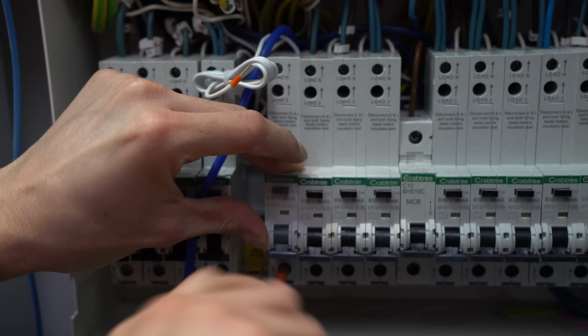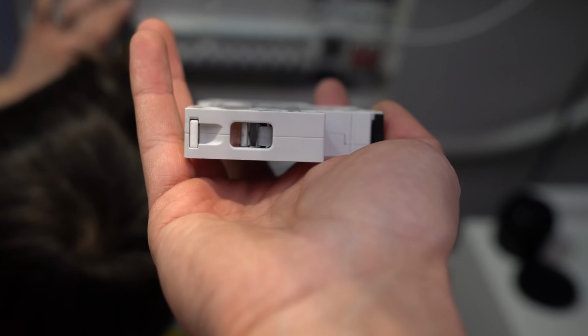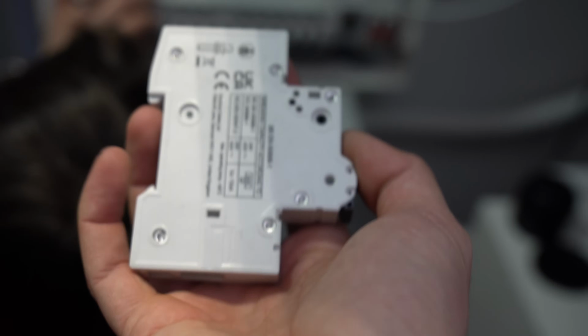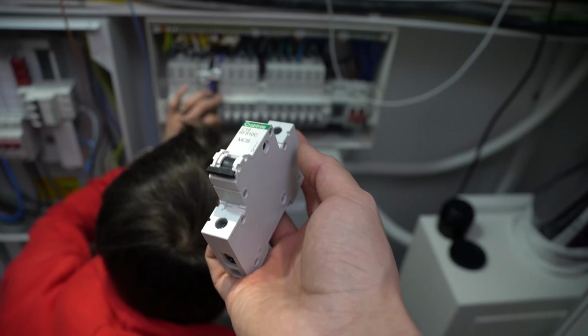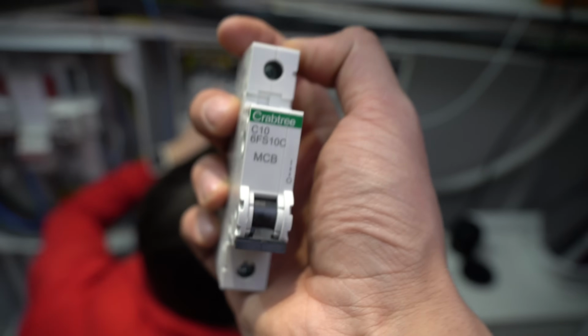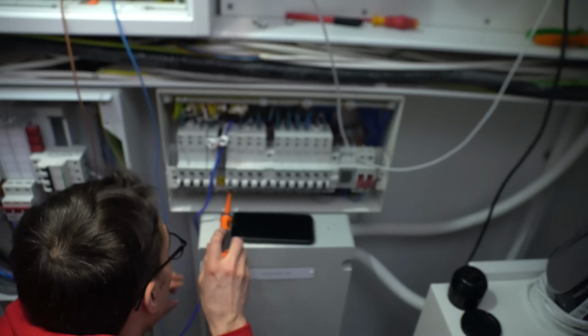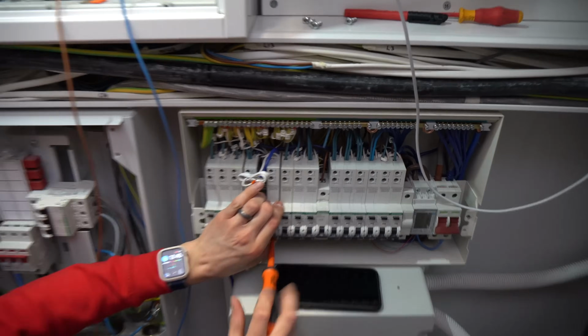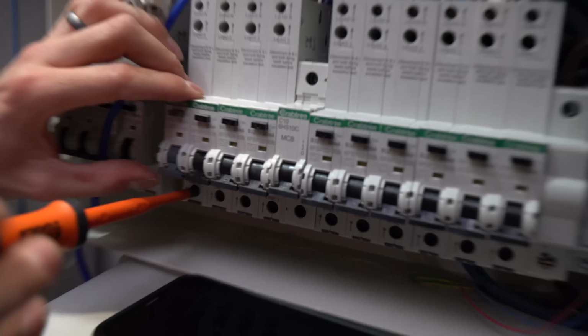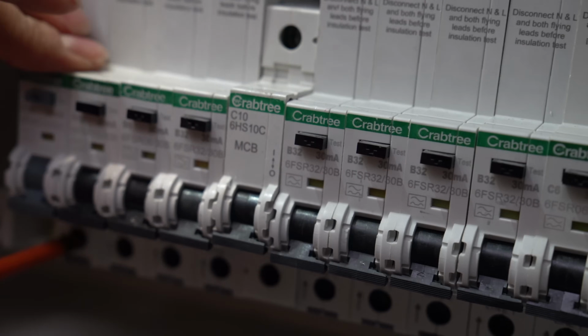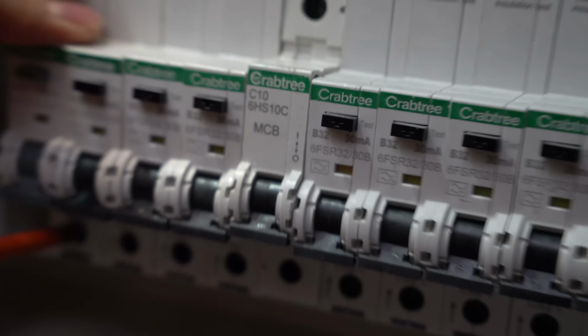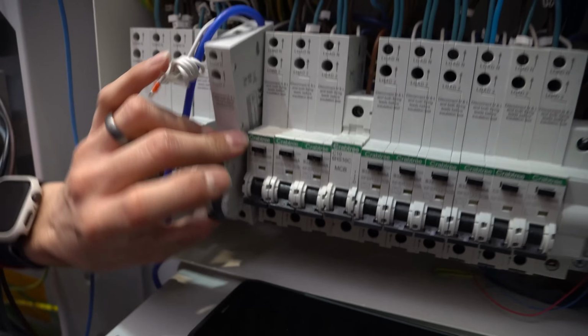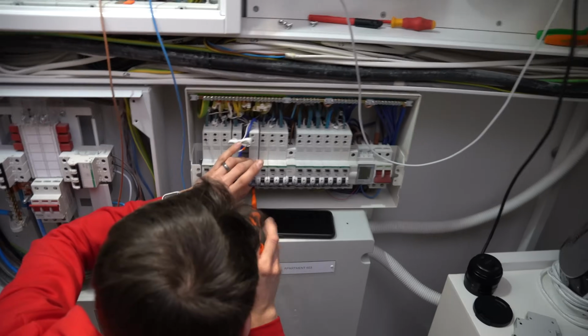So it's important with these boards to make sure that it's not just the same brand, but the same type. Because you see the bottom of this breaker here is slightly different, and the measurements for it are slightly different as well. So you're going to find, one, it's not been type tested for the same type of enclosure as that, and two, you're going to see it just doesn't quite sit straight. So you see there, we've got another one to replace that because it just doesn't quite fit right. And I know that sounds like we're being really fussy, and we are, but in a property this beautiful, you're allowed to be a bit fussy.